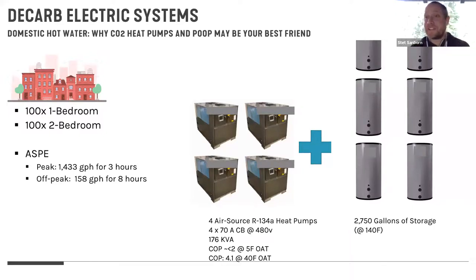One of the things you can do with the system though, if you want to, is add more storage if you've got the space for it and you can stomach that cost, and you can lock out the heat pump production to only daytime hours. So if you have enough storage to coast through the evening and that first 3 hour peak run, and then let your heat pumps run full on for 12 hours during the day, that's another option. You're going to see increased outside air temperature, higher COP, higher thermal performance from your heat pumps. It's still a costly option. It's a lot of air source heat pump, it's a lot of storage.